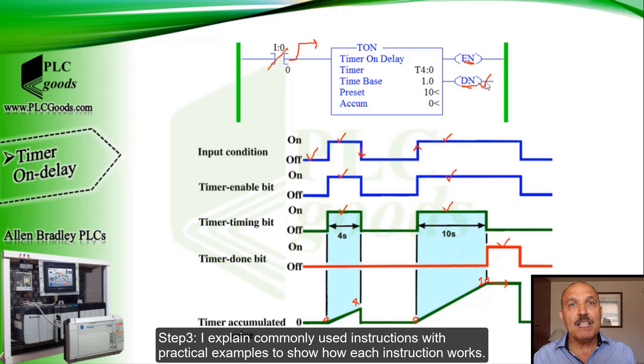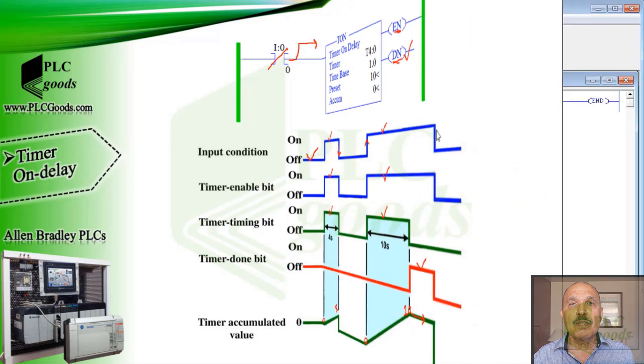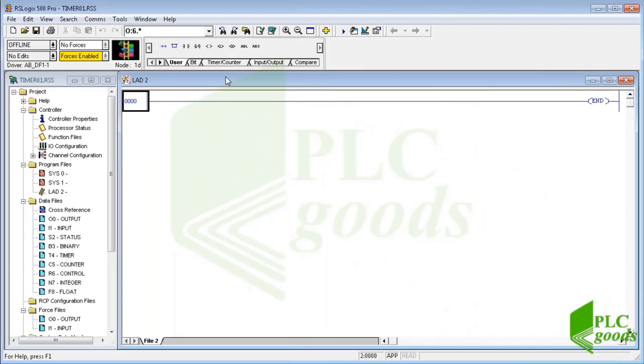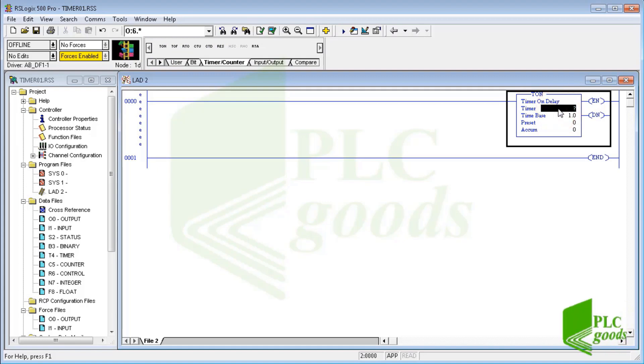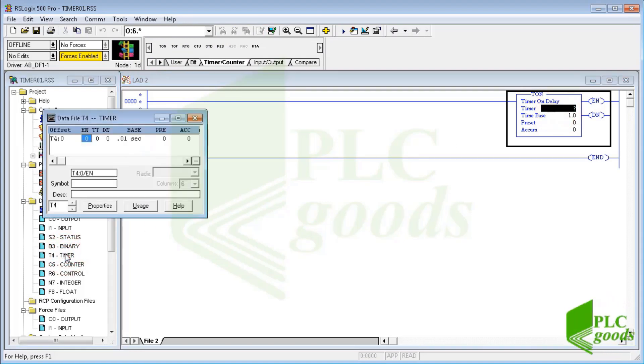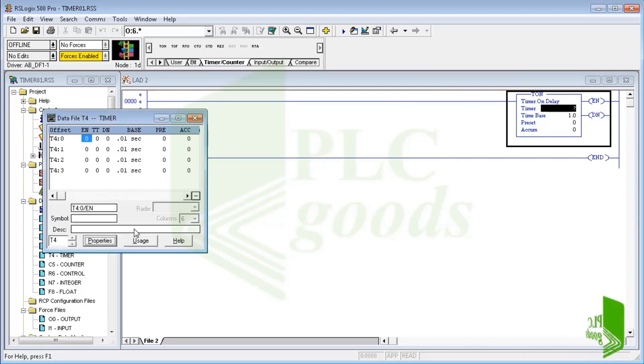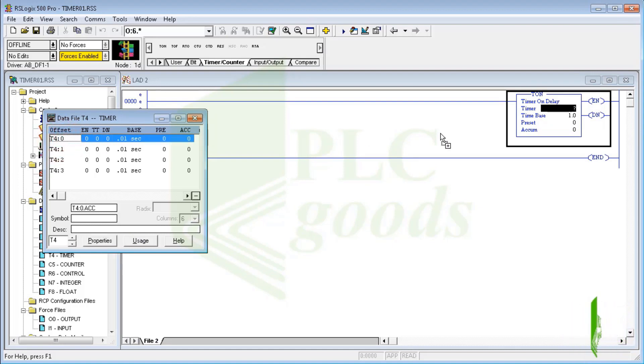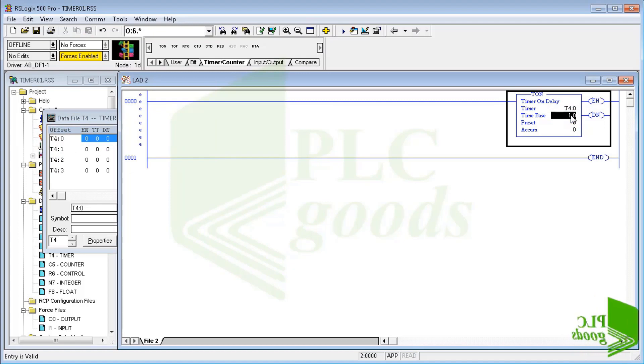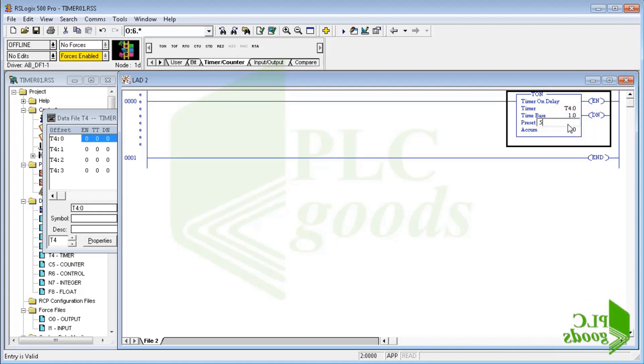Step 3: I explain commonly used instructions with practical examples to show how each instruction works. Let's test an on-delay timer — click here to insert one. The inserted timer needs a timer address. In data files, select the timer file. As you see, there is only one timer currently, but we can have up to 256 timers. This is an advantage of using PLC, because we can have many timers without paying any money. I select the first one, and let the time base and preset value be 1 second and 5, so the overall time will be 5 seconds. I then insert a normally open contact to enable the timer.